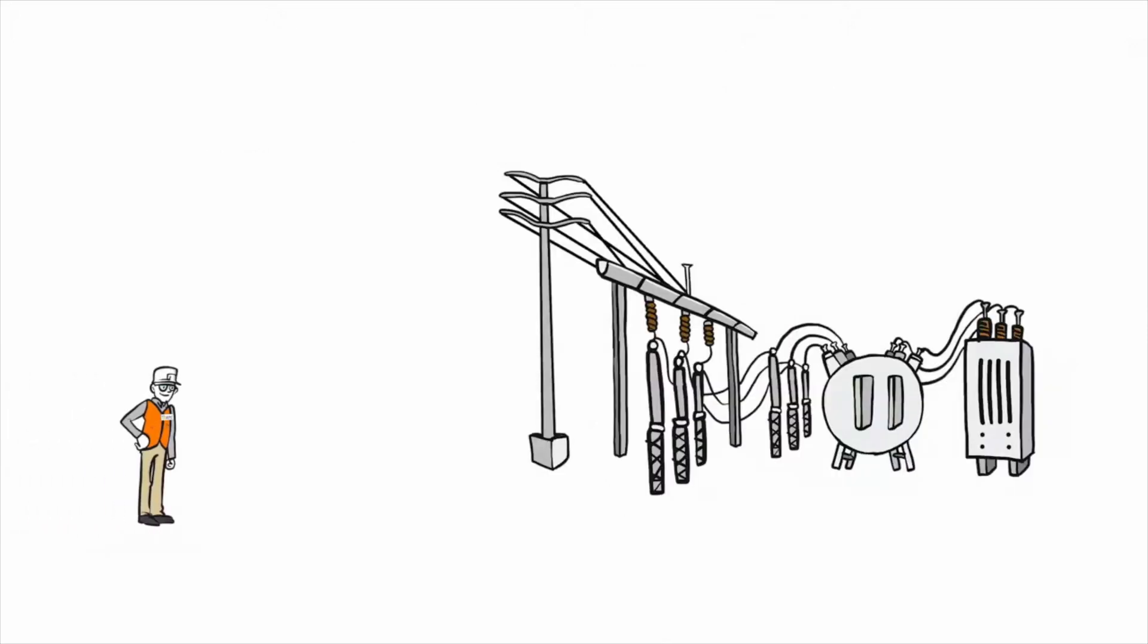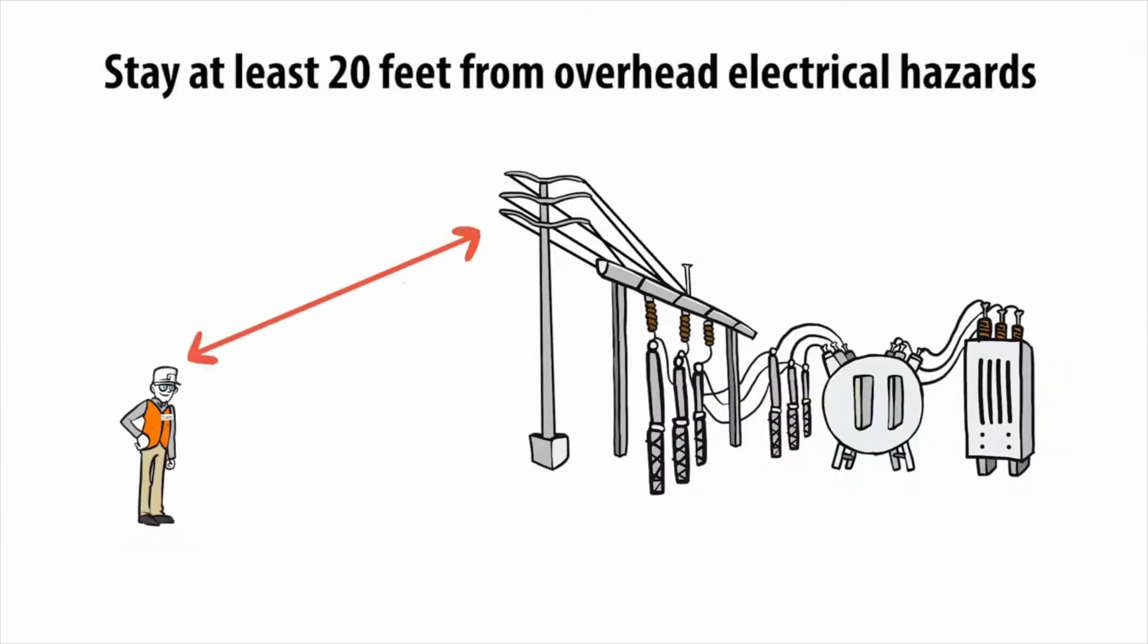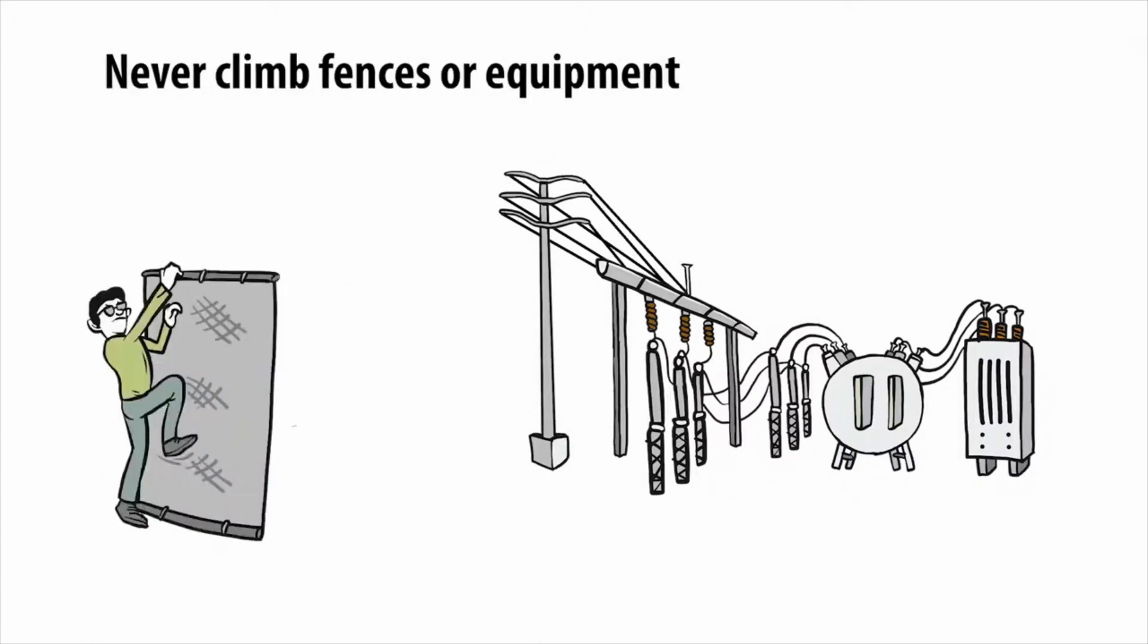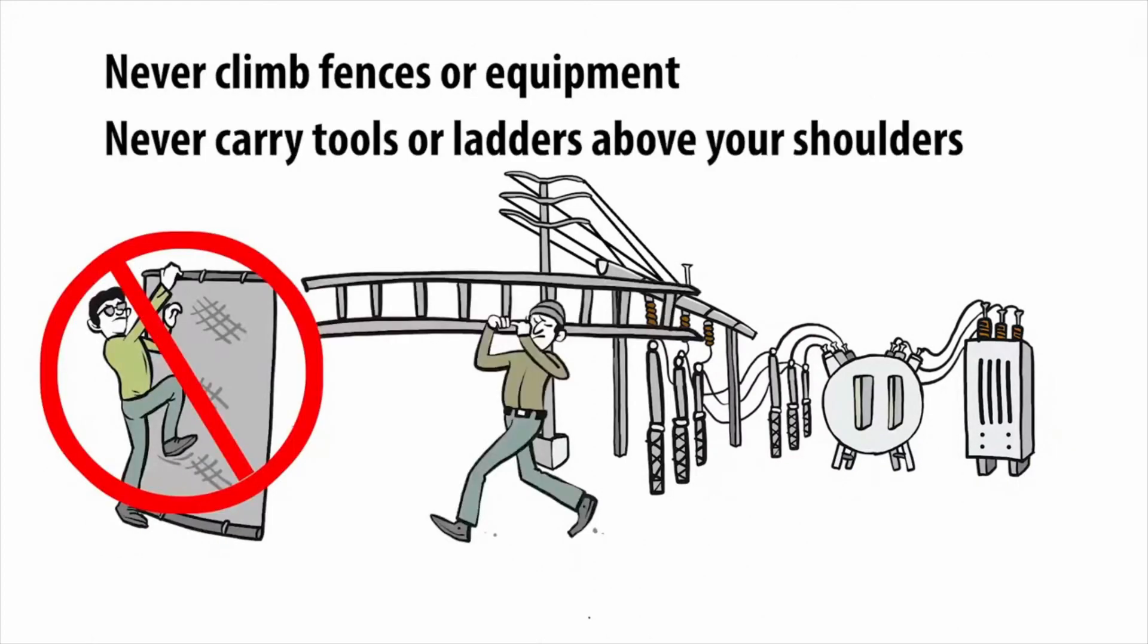Inside a substation, stay at least 20 feet from overhead electrical hazards. Never climb fences or equipment, and never carry tools or ladders above your shoulders.